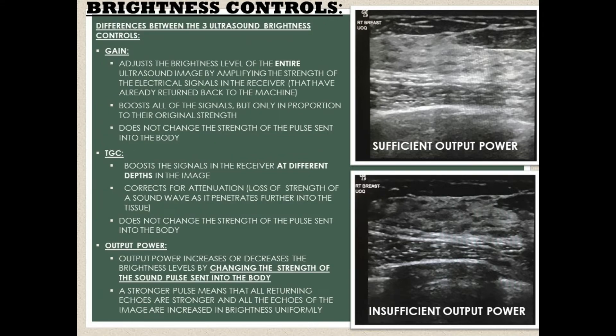Let's compare and contrast the three brightness controls on an ultrasound machine. The first ultrasound brightness control is known as gain, and gain adjusts the brightness level of the entire ultrasound image by amplifying the strength of the electrical signals in the receiver.